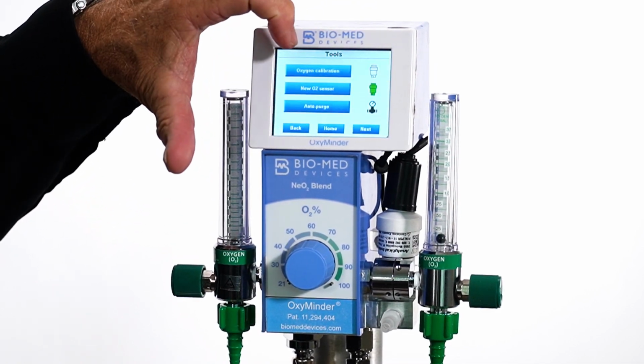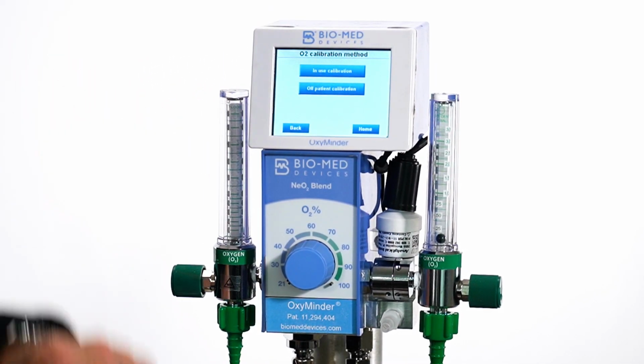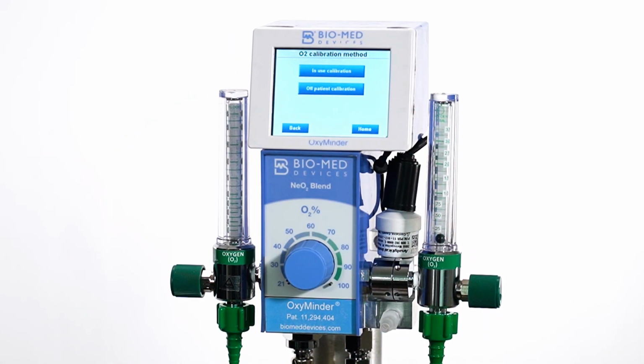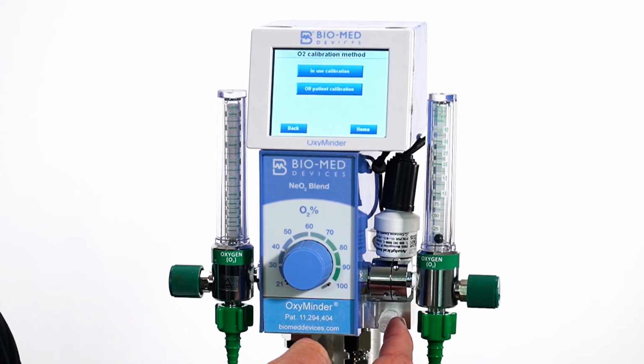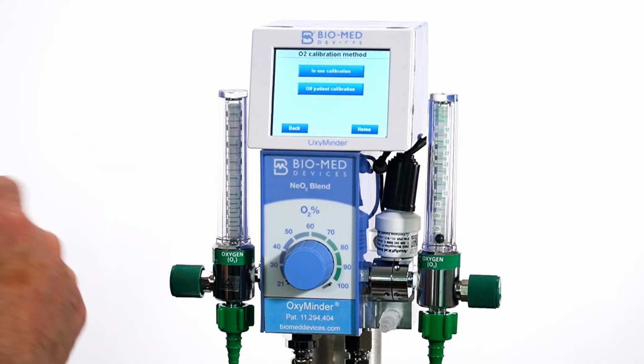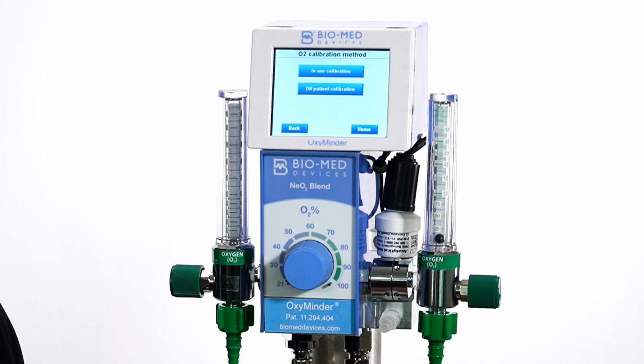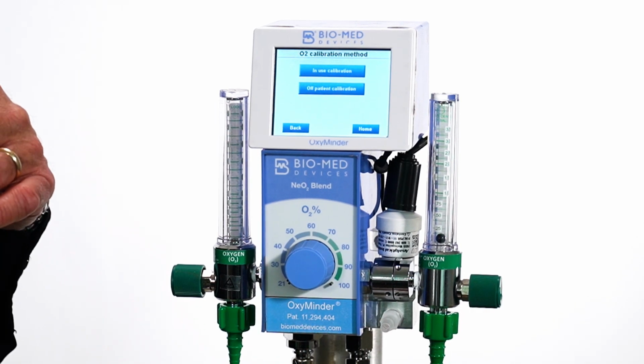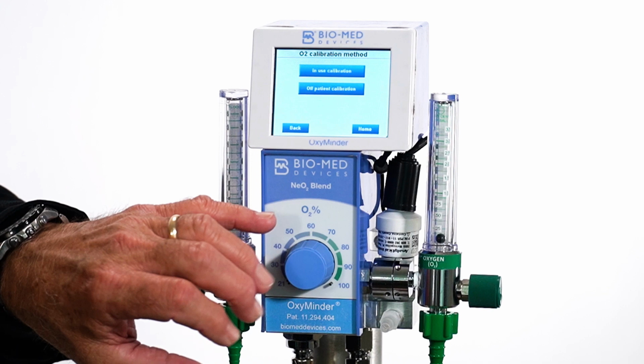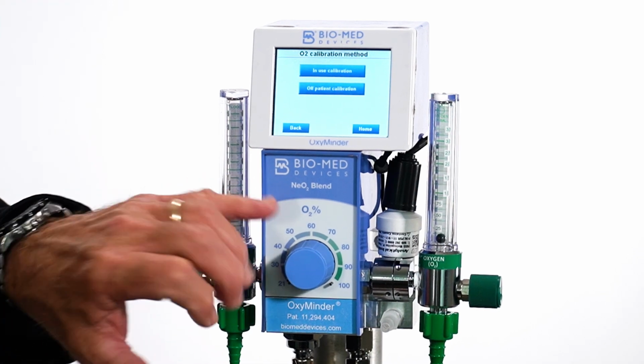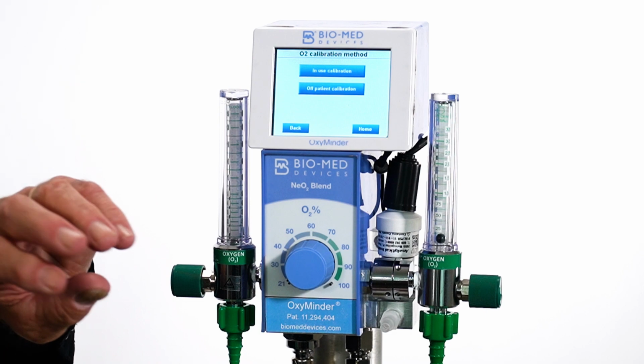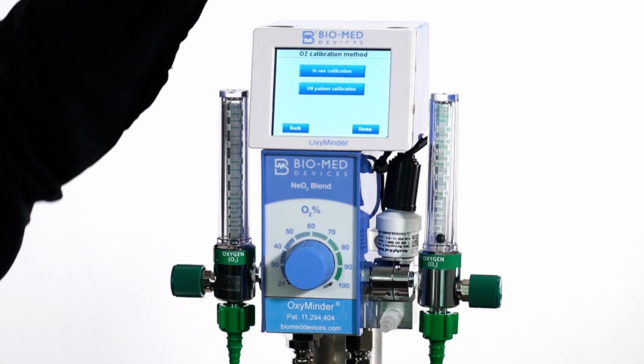Now, as I said, we can actually do an oxygen calibration while the patient's on the blender. What we're basically going to do here, and I won't do it for this demonstration, we're going to provide 100% oxygen from a flow meter to this port right here when it tells us to, and then we'll do 21% from a flow meter from the wall to this port. That way, if we feel the need to do a calibration while the blender's in use, we don't have to swap it out. We can do the calibration and then continue.